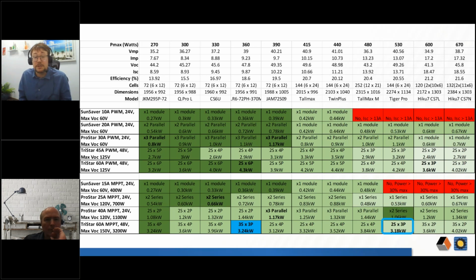So that's another consideration. Probably one of the most common ones that we've seen is for rapid charge and discharge cycle applications, where it's all about how much energy you can throughput on the battery, and having some of these lithium batteries that can truly support 2C continuous charging. For those of you that don't know what that means, basically double the rated capacity of the battery in current input, something definitely lead acid batteries cannot do as well.